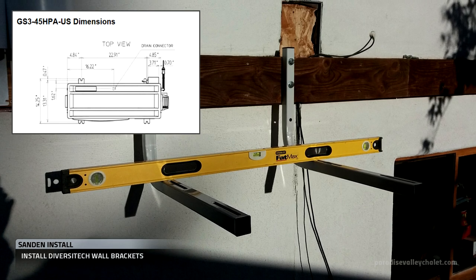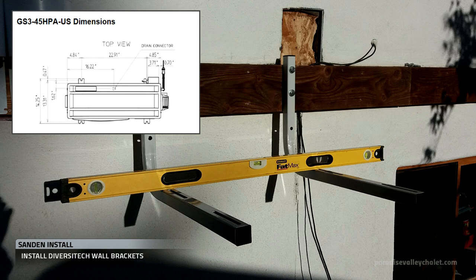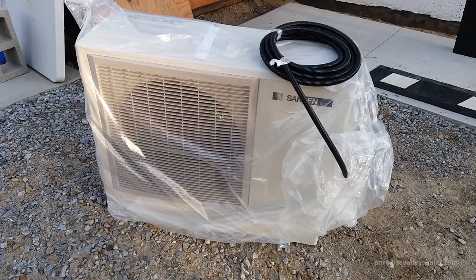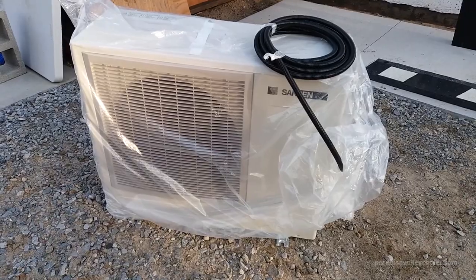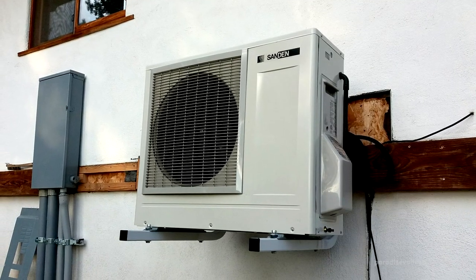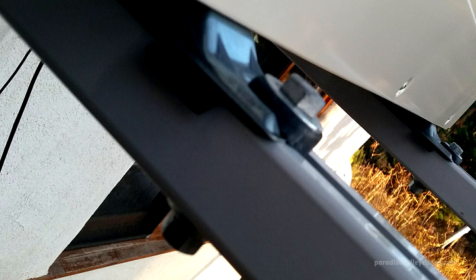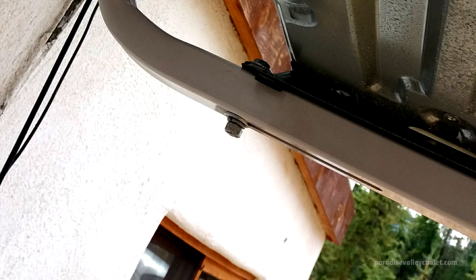On center to on center is 22.91 inches, so we're square and level, and now we're going to place the heat pump on those brackets. Here's the Sanden — about 108 pounds. Not that heavy of a lift, but you can't tip it, so you pick it up square and place it. On the bolts going into the building and on the bolts locking the Sanden to the L-brackets, we have anti-vibration padding and anti-vibration washers.